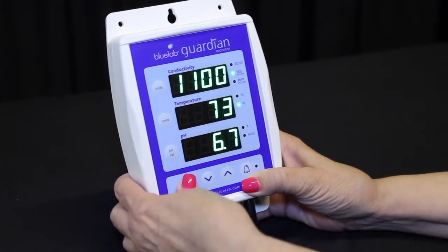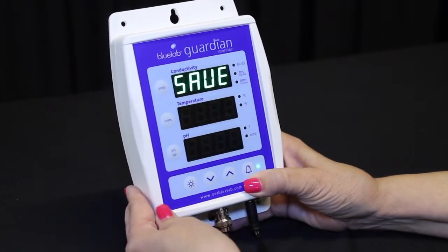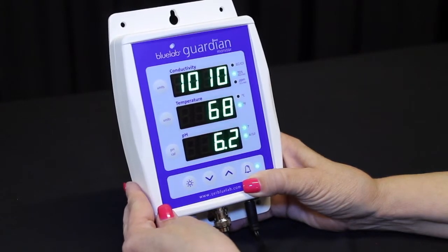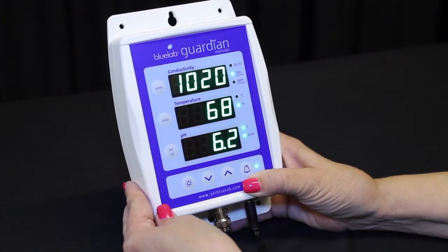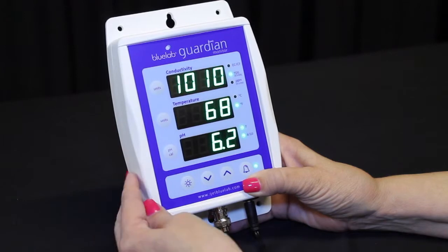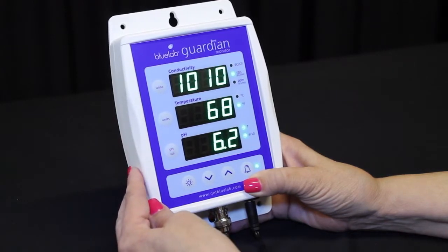Press the brightness button once. All three windows display auto for one second, then save will show in the conductivity window. The alarms are now automatically set and the alarm LED will glow, indicating it is active.